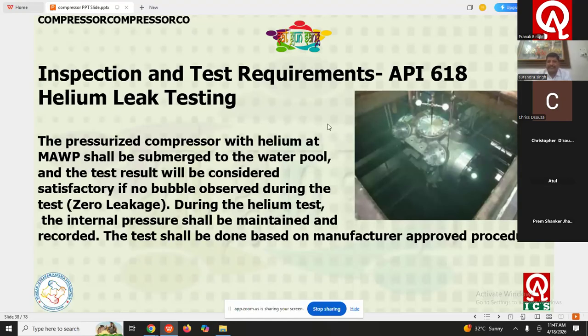This is a helium leak testing, nothing special. It's actually a pneumatic testing method. But why do we use helium? Helium is a much lighter gas compared to air and nitrogen. When we fill this with air, it may not come out from the leakage point, but helium, since it is such a light gas, will. So we use helium as the media during this pneumatic test.